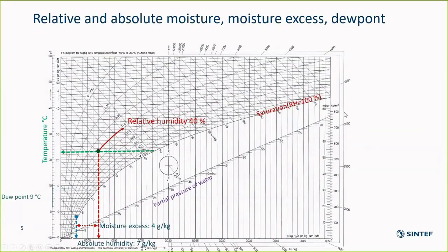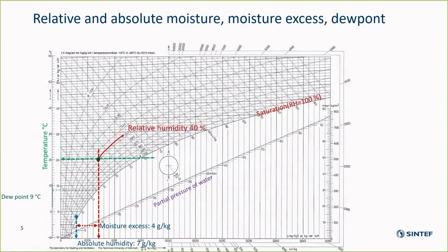A note on different ways of measuring moisture. Relative humidity is absolutely a useful measure, but in many situations it's more interesting and perhaps more practical to use other ways of stating moisture content, like absolute humidity, moisture excess, or dew point. As you all know, the relative humidity changes when the temperature changes — a relative humidity could increase by eight percent when you decrease the temperature from 23 to 20 degrees.